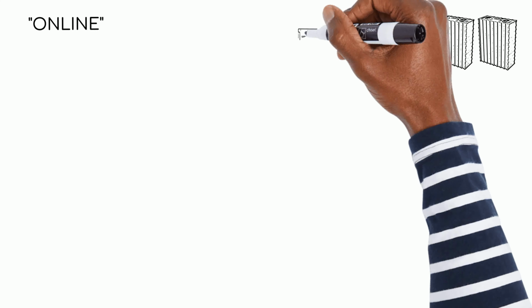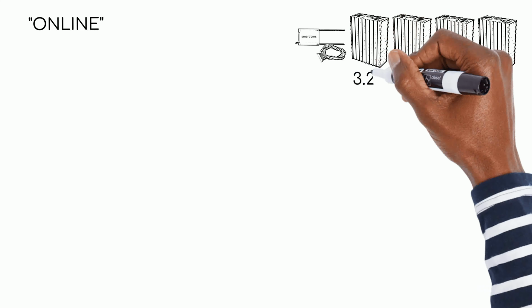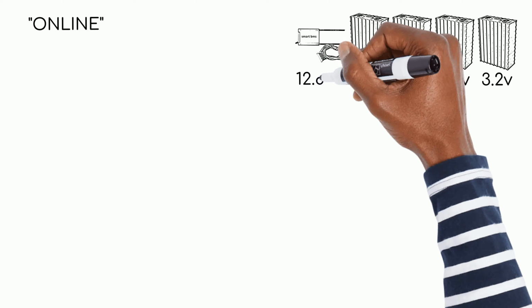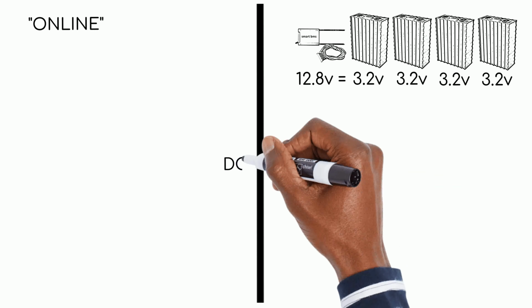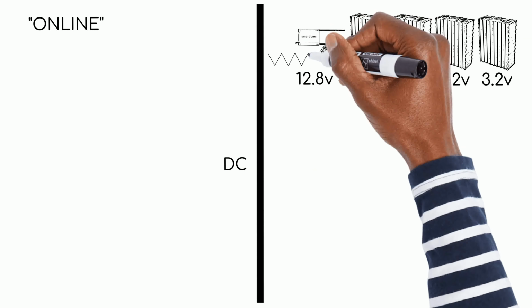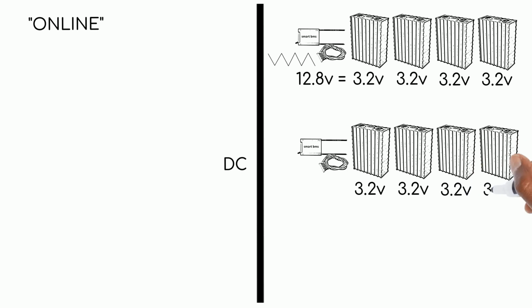Now let's talk about the online topology, in terms of synchronization and general logic. There is no central BMS. Each set of cells is controlled by its own battery management system. Depending on the task, the cells in the set are connected in series or in parallel. Each of the sets is an independent battery, connected to a DC bus.